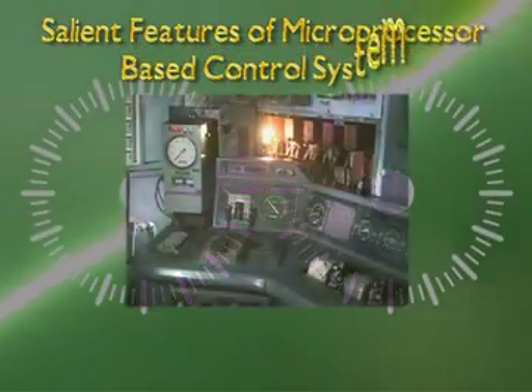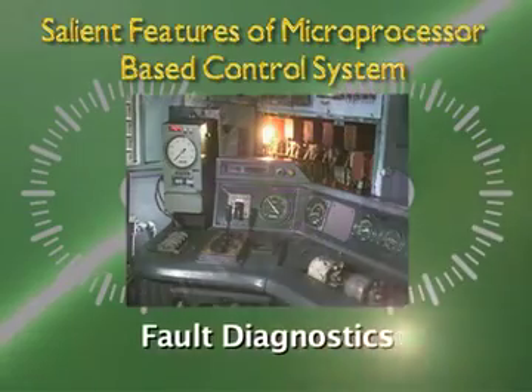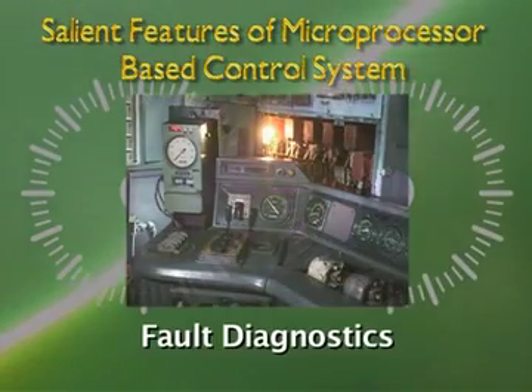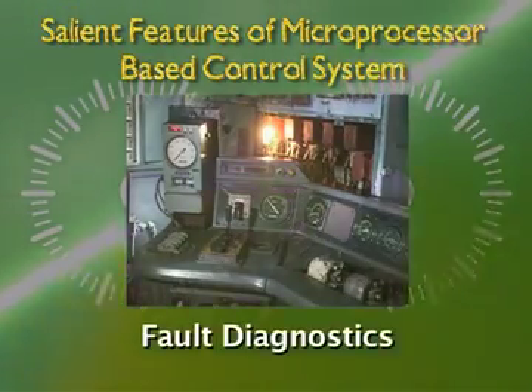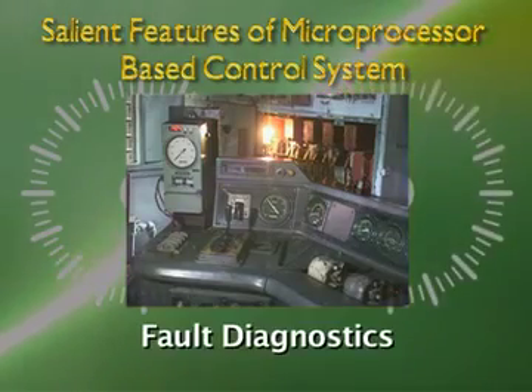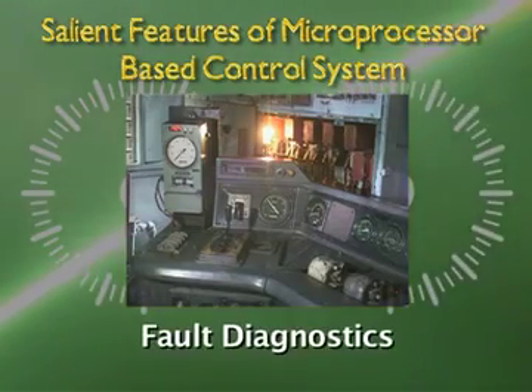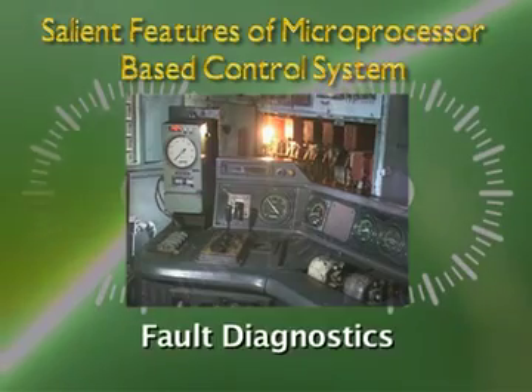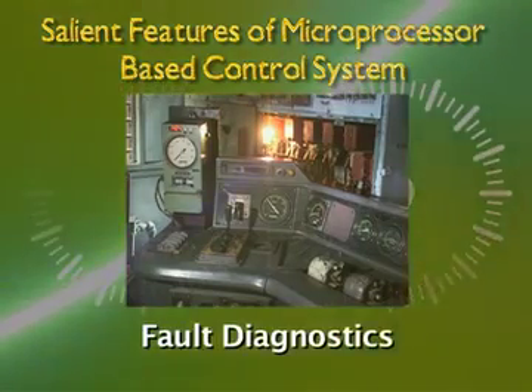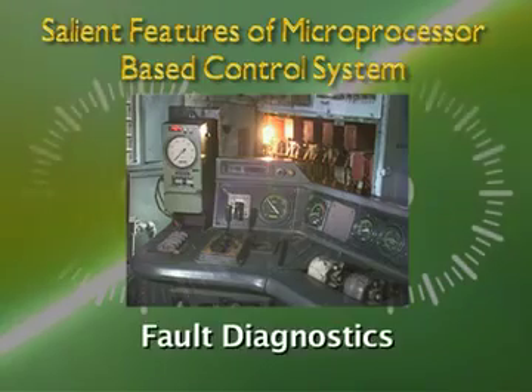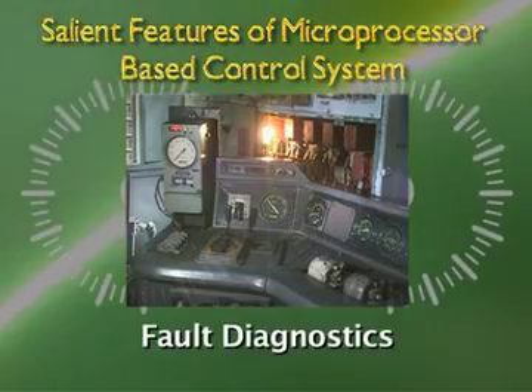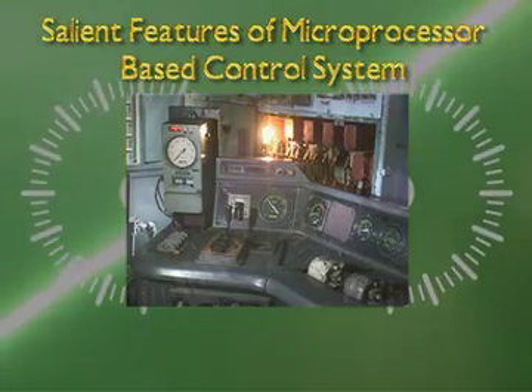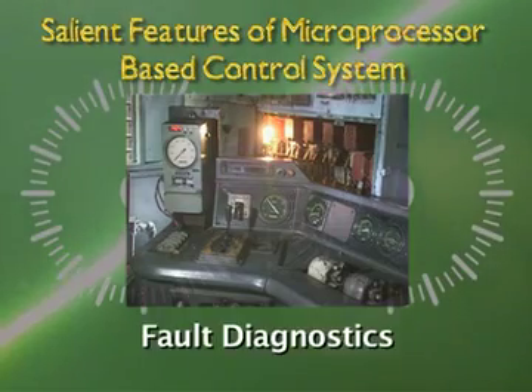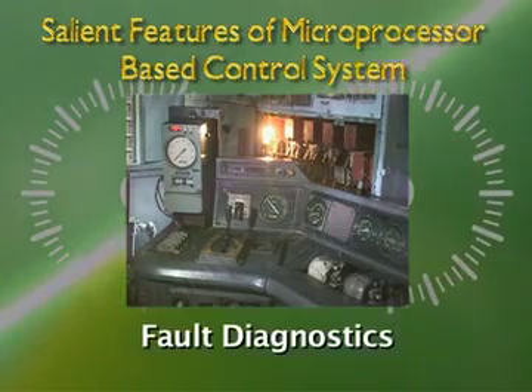Salient features of microprocessor-based control system. Fault diagnostics. Microprocessor-based system has fault diagnostic capabilities. The system continuously monitors various operational parameters and checks for abnormalities in the functioning of various traction equipments. The fault is displayed on the display unit along with restrictions imposed because of the fault. For information of the driver, the fault code along with real-time and date stamp is logged in the error log memory.